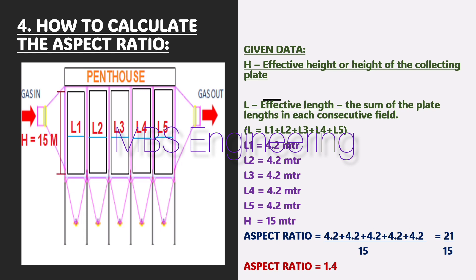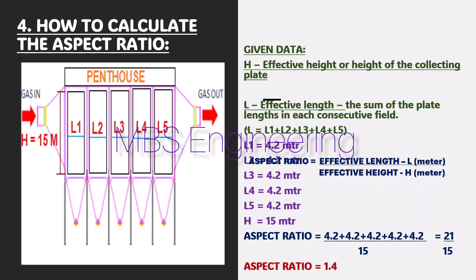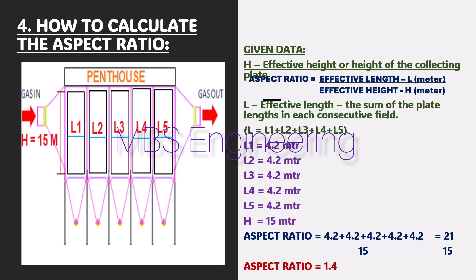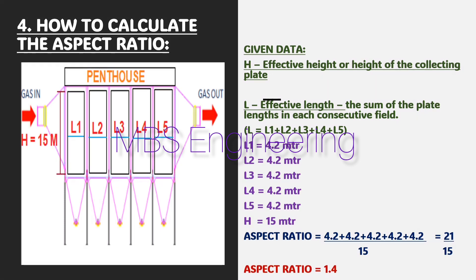Then, the aspect ratio equals effective length (L1 + L2 + L3 + L4 + L5) divided by effective height H. That means 21 meters divided by 15 meters. As per the given data, the aspect ratio is 1.4. The aspect ratio is usually greater than 1 for high efficiency ESPs, and should be high enough to allow the rapped particles to settle in the hopper before they are carried out by the gas flow.